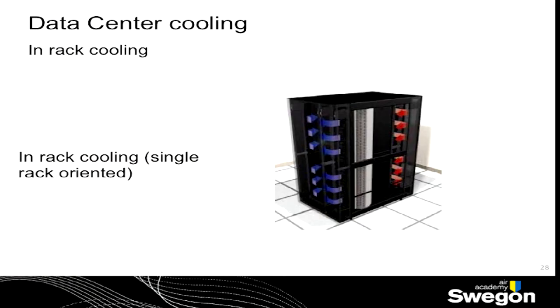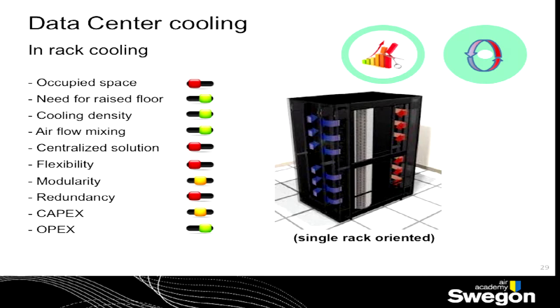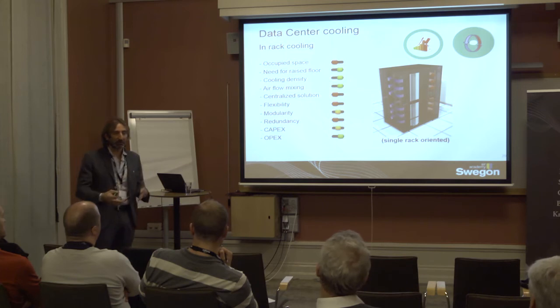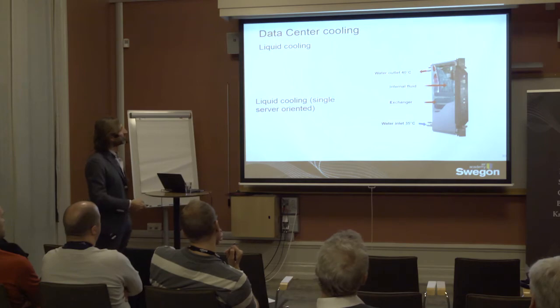Another step in efficiency in terms of recirculation is, of course, the in-rack cooling. The in-rack cooling provides the cooler just inside the rack. And this minimizes the problems coming with recirculation because it avoids it completely. There's no possibility. But, of course, it has a very low flexibility because I have to combine them one by one. And in terms of redundancy, it is quite risky because if it fails, it means that the server will fail. Okay, I can mitigate this with a 2-coil system, but the fans are just inside. So you have to be very careful in the decision of what system you're using. And the last one, we have gone deep inside of it.